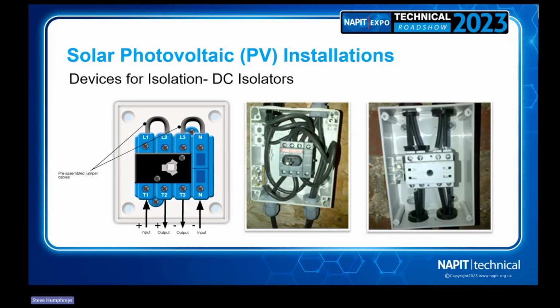One of the reasons that we do get problems with DC isolators, and it does cause the majority of faults resulting in fires, that data is true. That's not to say it's a fault of the equipment or its intended use. It's because what we get is things like this. So you can see on the left hand side you've got a DC isolator with your jumper cables pre-assembled in there, because obviously when we get DC arcs, those tend to be a bit more ferocious, for want of a better word. So we have these jumper cables in to diffuse that arc in stages, and the connections have got to be right into that DC isolator. And what you can see on the right hand side there is some installers that have not understood how to install these things.